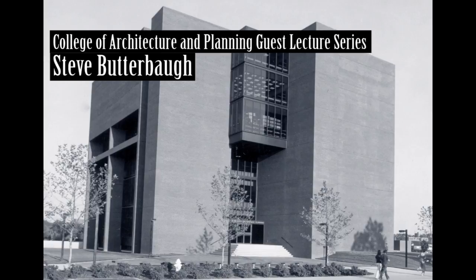In other cases, typical proposals are adding storm windows, insulating the attic, interior paneling with insulation, vestibules, tuck pointing, reputting of windows, caulking, sunshades on the building exterior, blocking up windows, replacing inefficient light fixtures with efficient ones, lowering the hot water temperatures, installing flow control devices on showers, adding a small water heater for kitchen use so that the water temperature can be turned down on the larger general purpose water heater, putting mechanical equipment or lights on timers so that their operation is reduced.